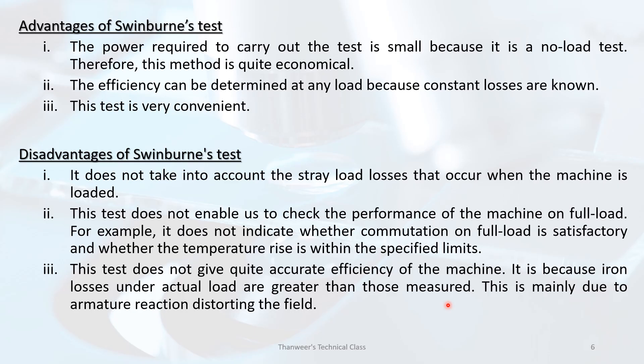Also, this test does not give quite accurate efficiency of the machine, because iron losses under actual load are greater than those measured at no load. This is mainly due to the armature reaction distorting the field.